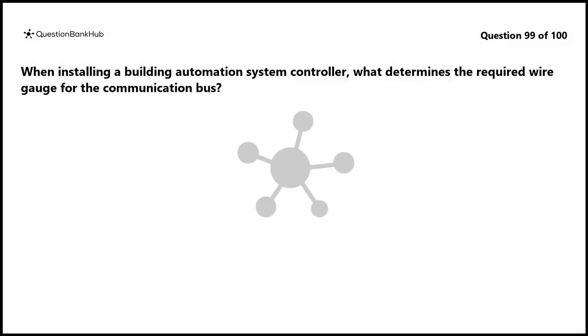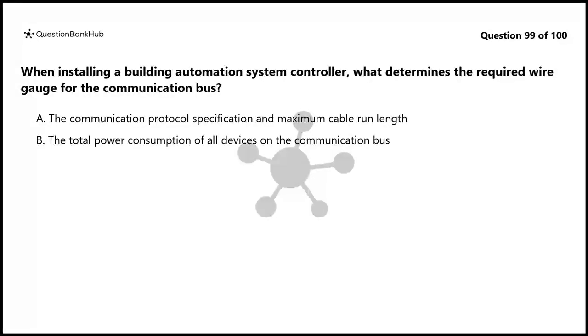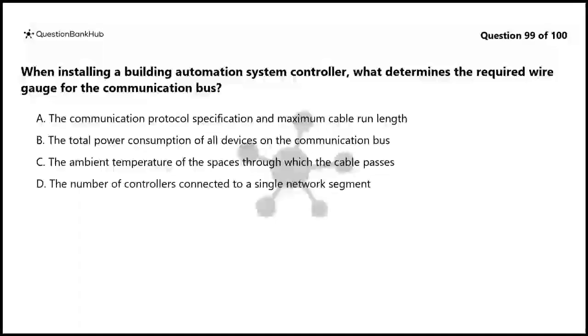Question 99. When installing a building automation system controller, what determines the required wire gauge for the communication bus? A. The communication protocol specification and maximum cable run length. B. The total power consumption of all devices on the communication bus. C. The ambient temperature of the spaces through which the cable passes. D. The number of controllers connected to a single network segment.